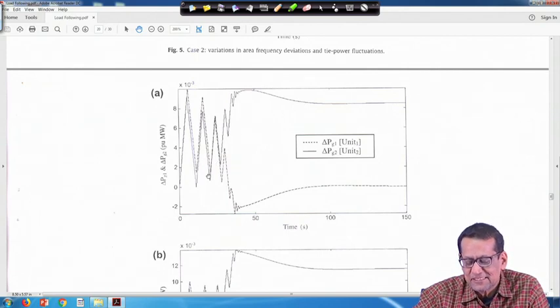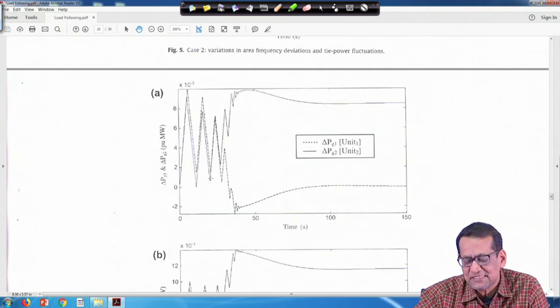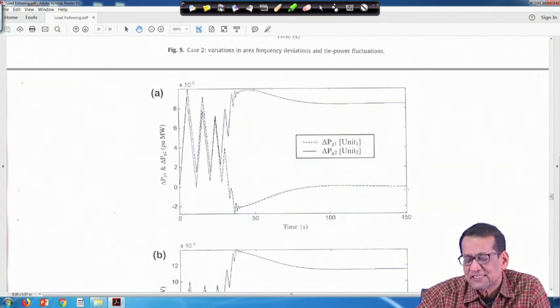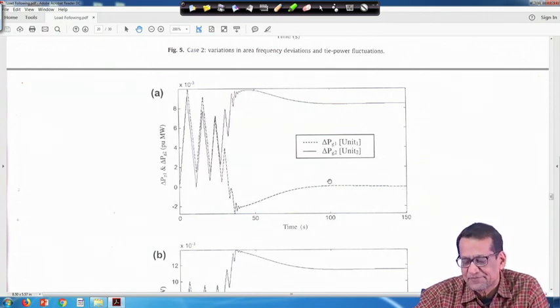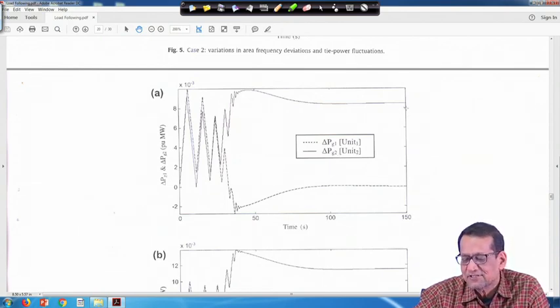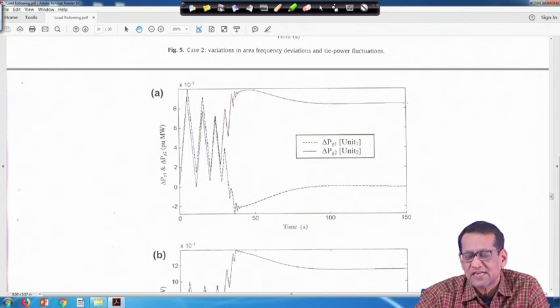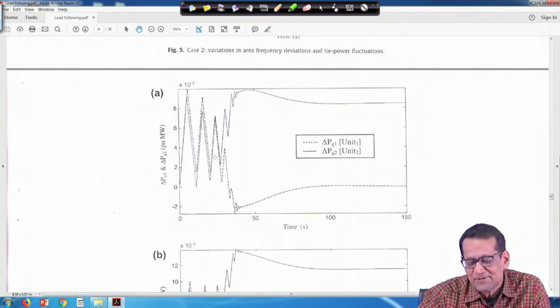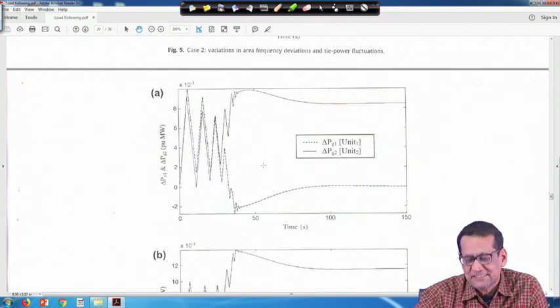During the transient time duration it is generating some power — increasing, decreasing — but finally it is settling to 0 at steady state. Delta PG2 also at steady state, whatever value was there earlier, 0.0085 per unit megawatt, it is coming to that value. Only thing is that the transient responses compared to case 1 have changed in case 2.